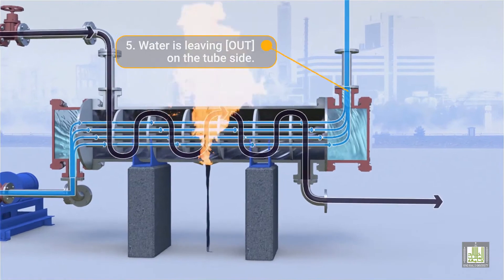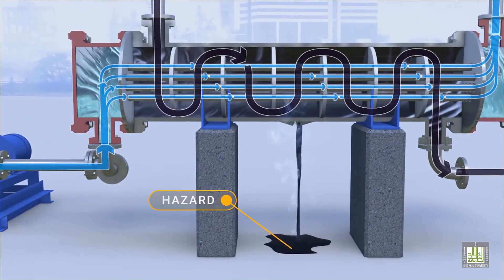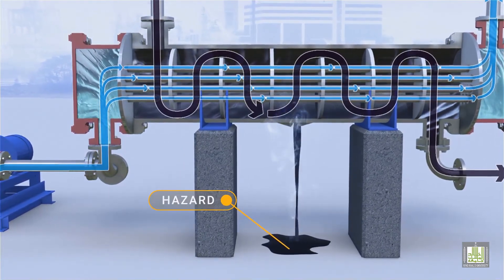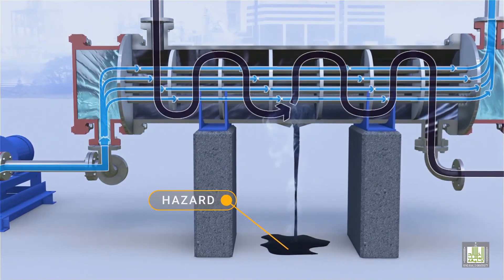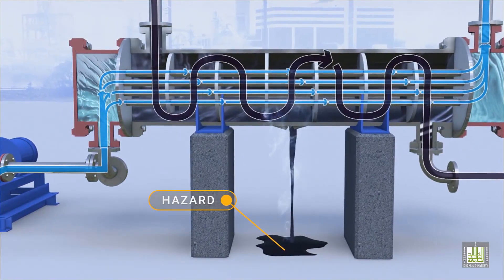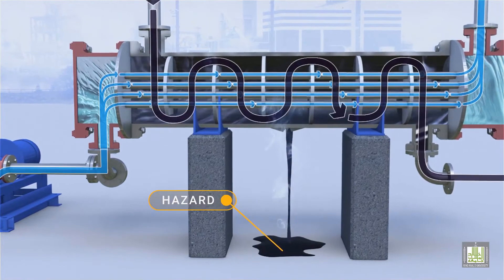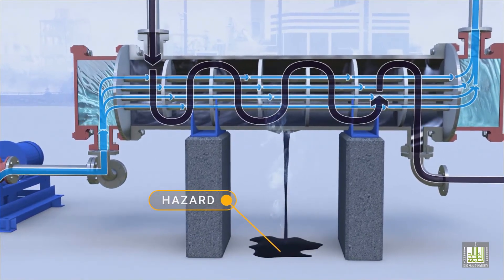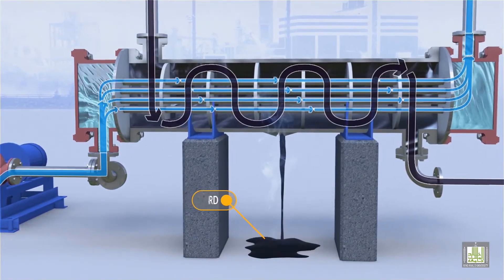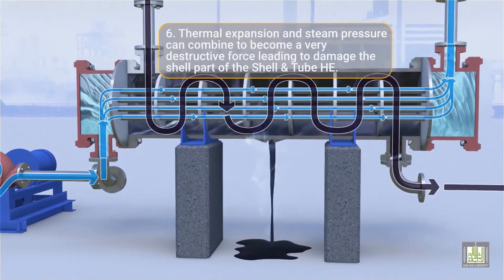The heat exchanger is typically provided with low or high point vents to remove water from the tubes or the shell. Uncontrolled mixing of water with hydrocarbons can generate high-pressure conditions and can damage systems that are not equipped with pressure-relief devices.